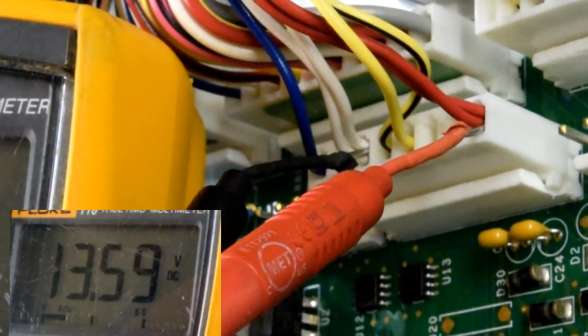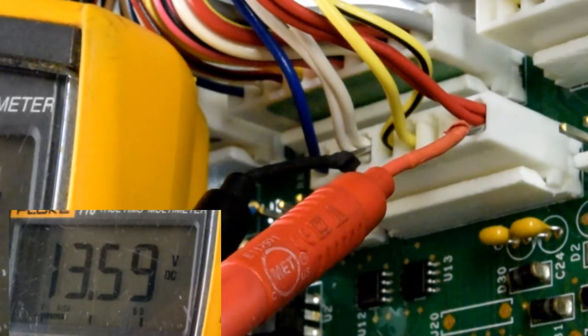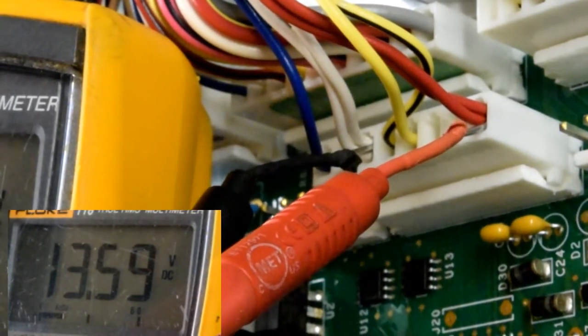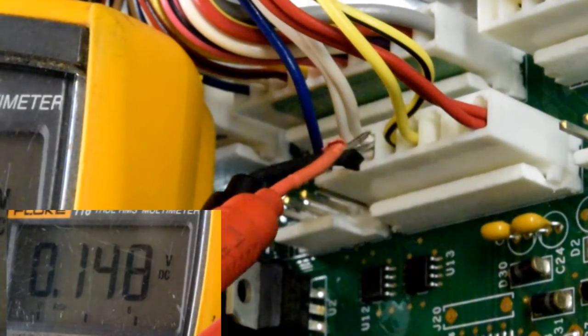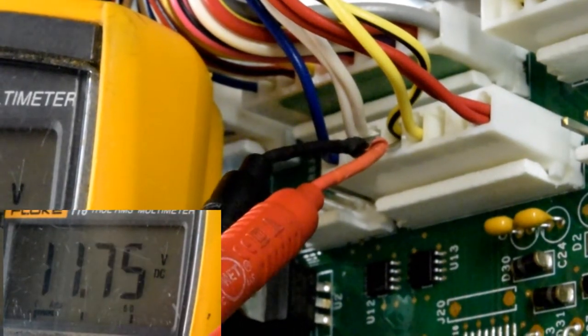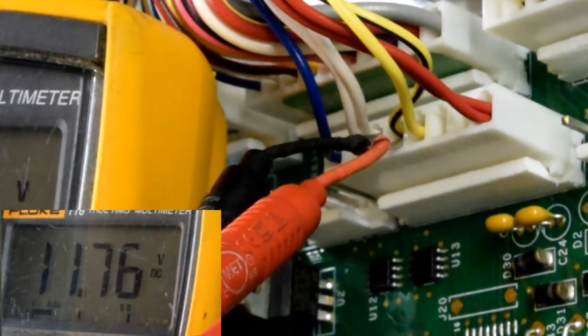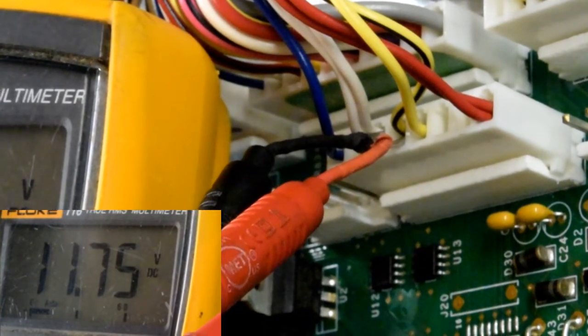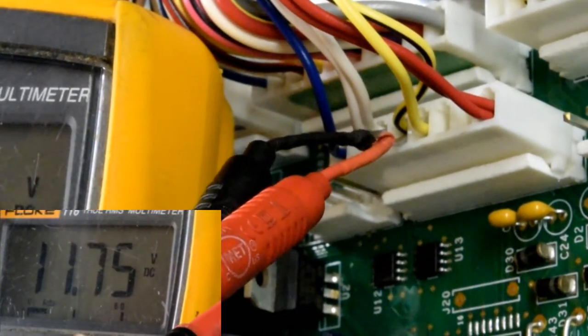Now for the second test, we're going to test the evaporator fan motor. Leave your black where it's at, remove the red, and put it right next to the black one on the right - pin number 4. Again, somewhere between 12 and 14 volts is fine, anywhere in that neighborhood. It's actually a variable speed motor, so it may flux.